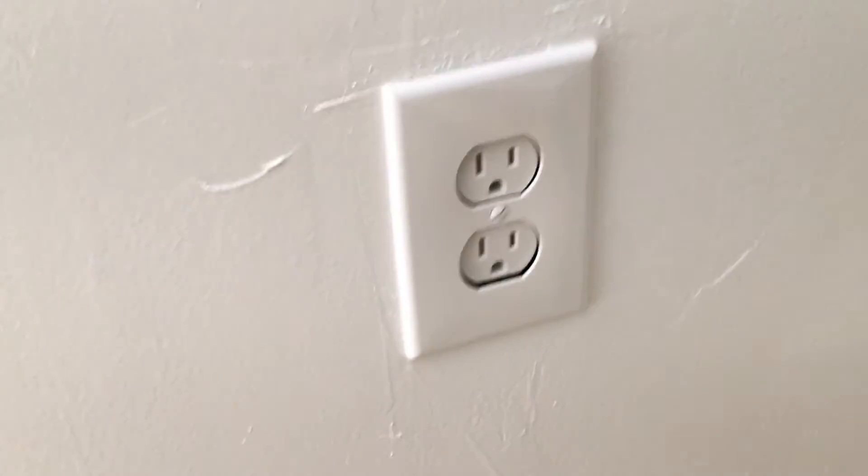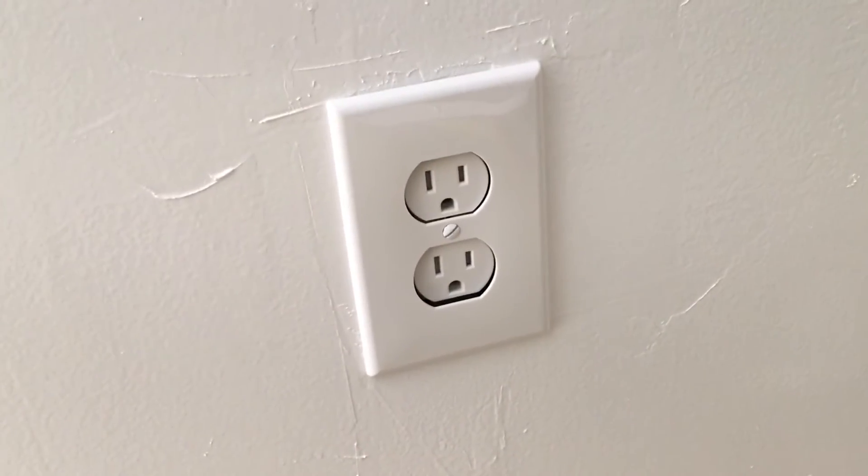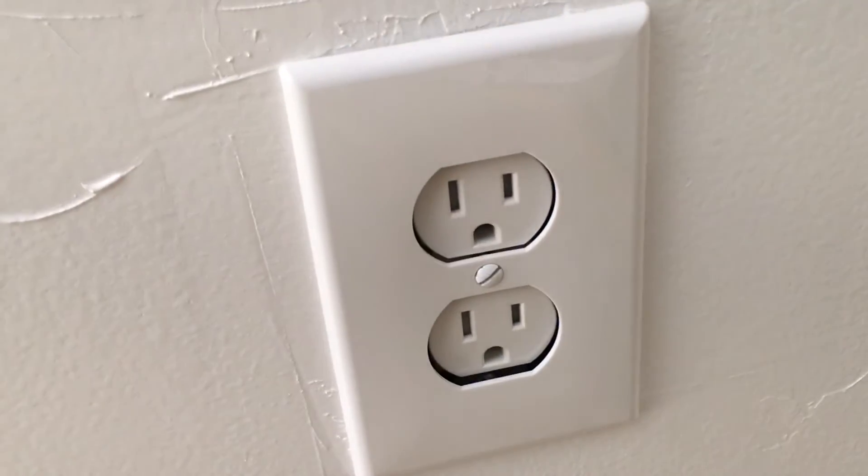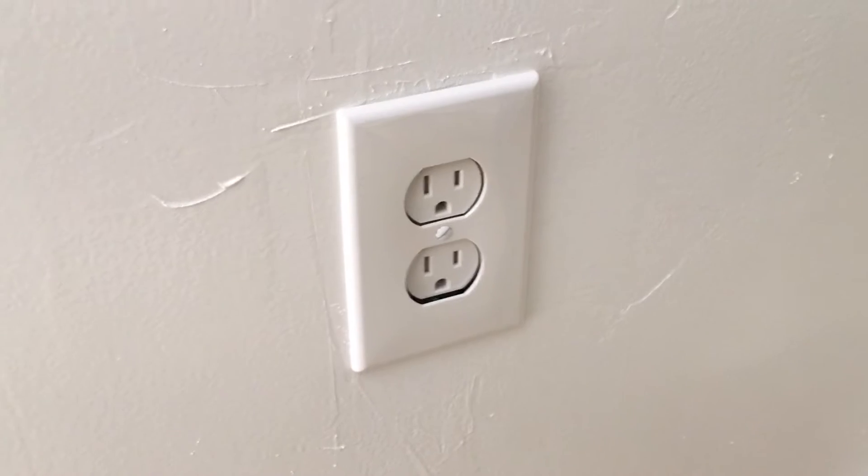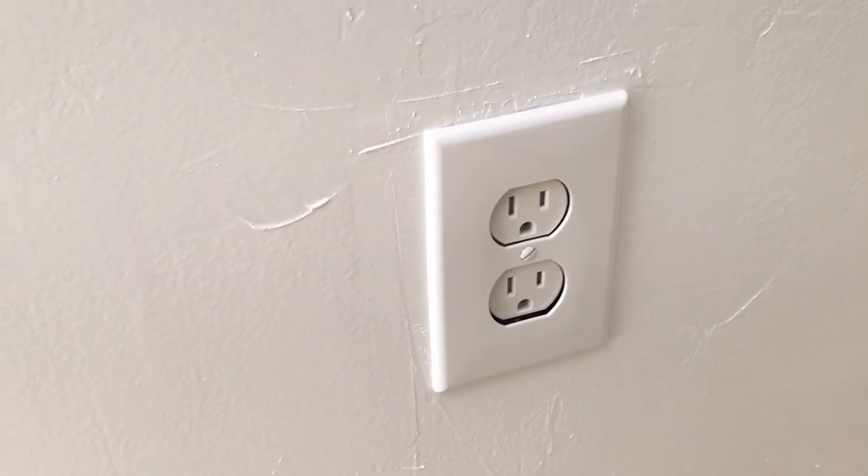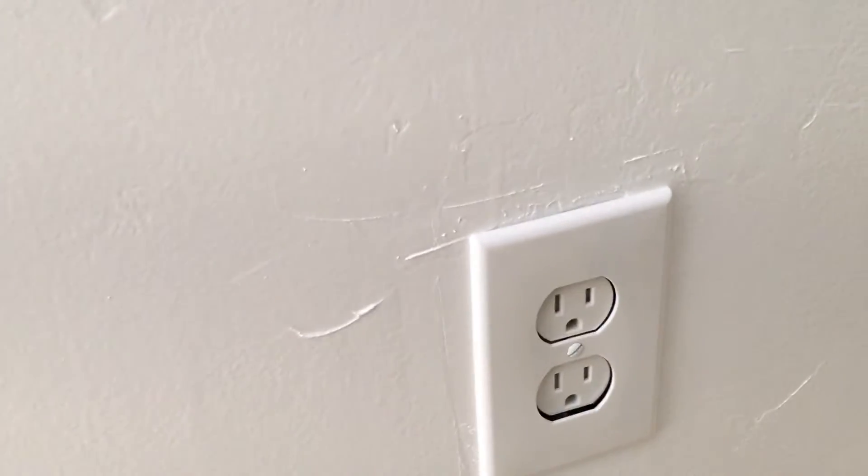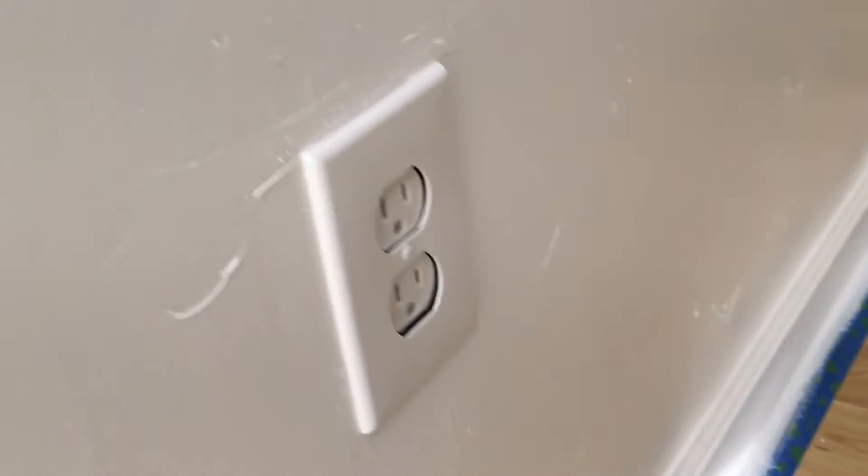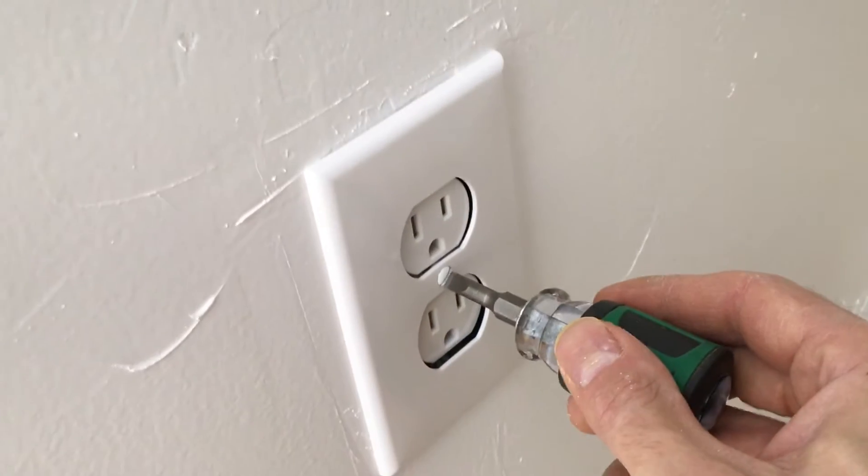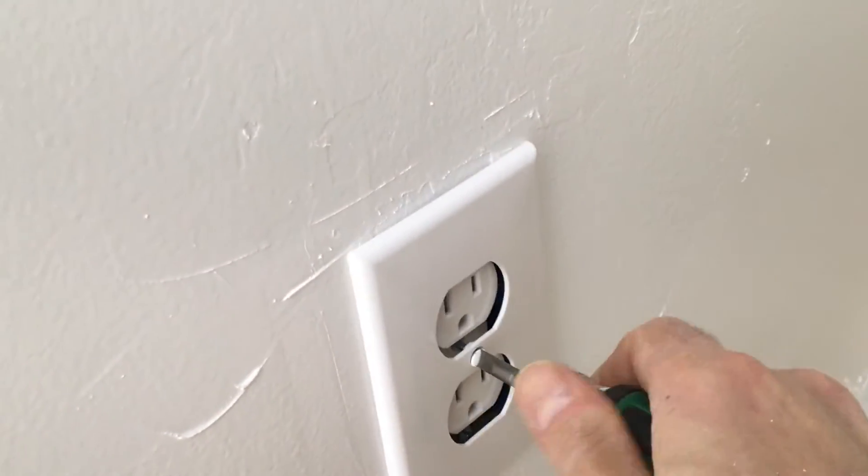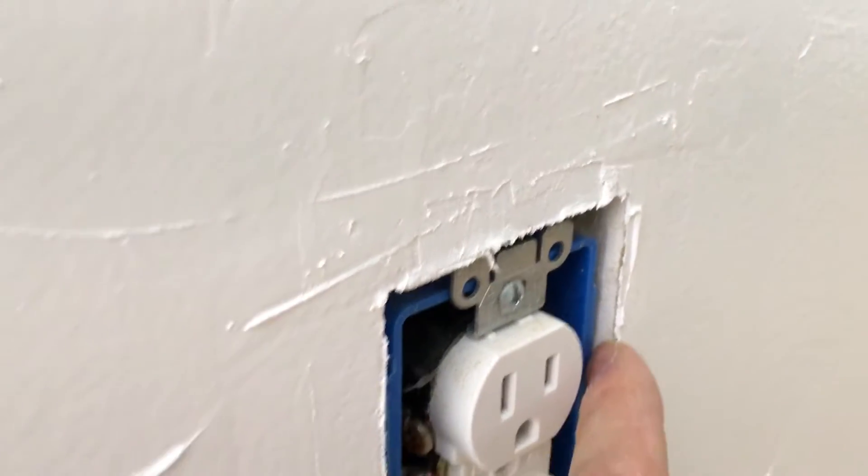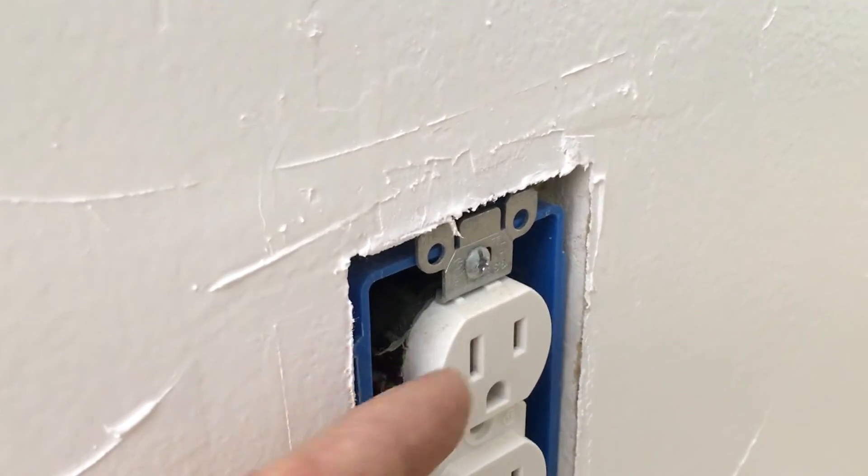Hey everyone, today I'm going to show you how to fix this. That doesn't look good. The outlet is recessed way too much. Looks horrible, really. So what we're gonna do is show you guys how to fix that. The problem is that the box isn't flush with the sheetrock here. You can tell there's a gap there. The box is supposed to be out about there.